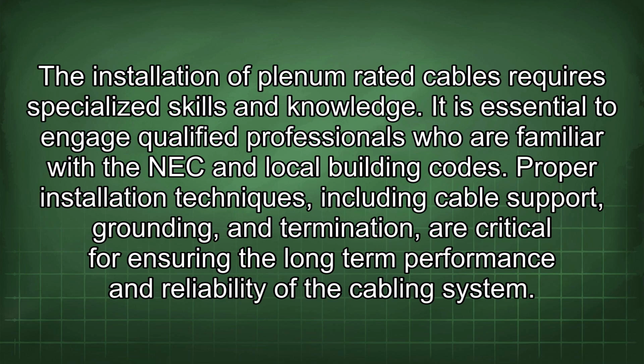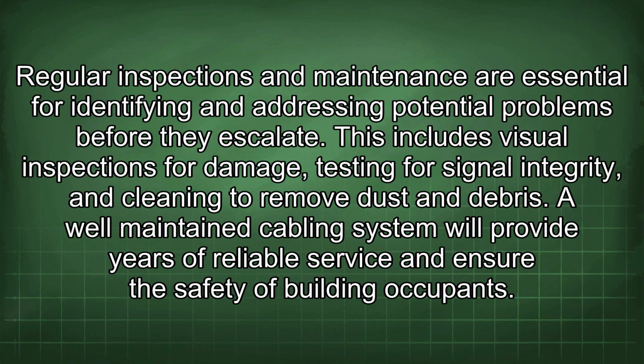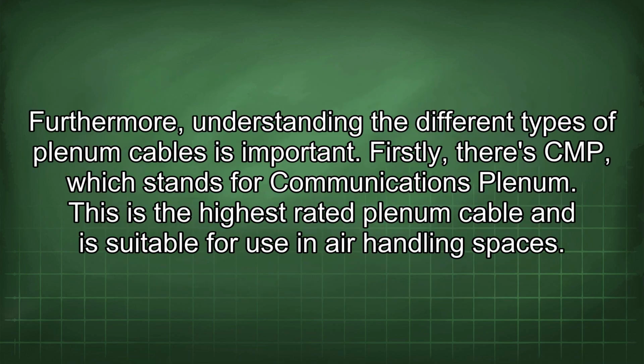Proper installation techniques, including cable support, grounding, and termination, are critical for ensuring the long-term performance and reliability of the cabling system. Regular inspections and maintenance are essential for identifying and addressing potential problems before they escalate. This includes visual inspections for damage, testing for signal integrity, and cleaning to remove dust and debris. A well-maintained cabling system will provide years of reliable service and ensure the safety of building occupants. Furthermore, understanding the different types of plenum cables is important.